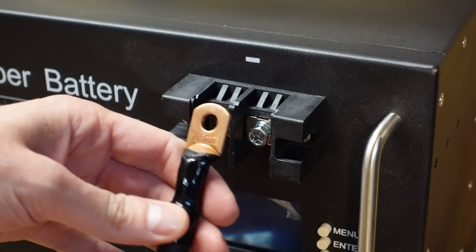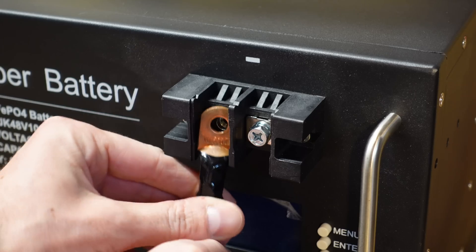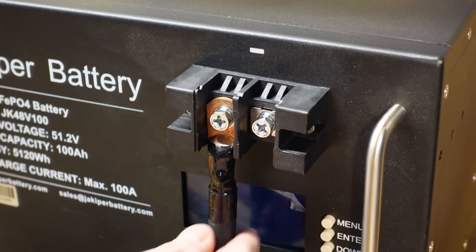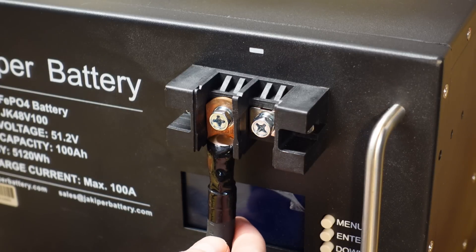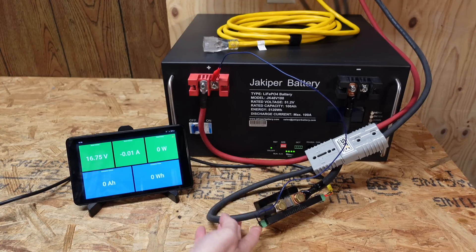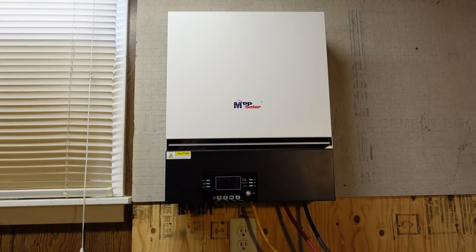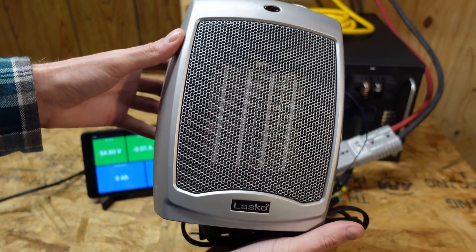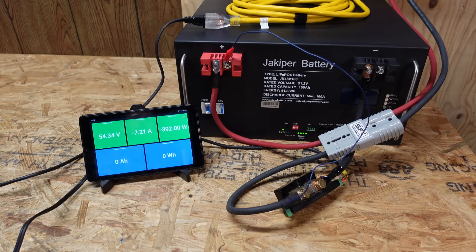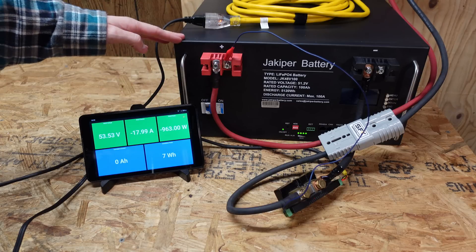I'm trying to connect cabling to this battery and I have some 1-aught cable, but the ring terminal is just a little bit too large to fit in. I can make it work, but these terminal blocks are kind of small if you're thinking of using thicker cabling. I definitely would not go any larger than a 1-aught size lug. So I've got my standard test setup here — cable going through a Batrium shunt with a display. We'll be using the new LV6548 inverter for load, with a space heater on low pulling around 975 to 1,000 watts, which gives us pretty close to a 0.2C rate. We have 17.9 amps, so we'll leave this running until the BMS in the battery shuts down.